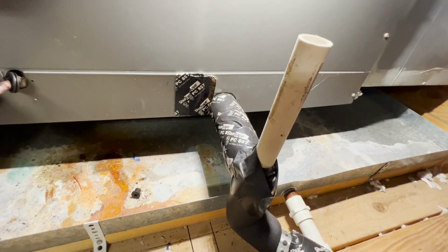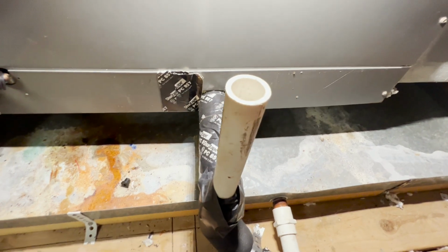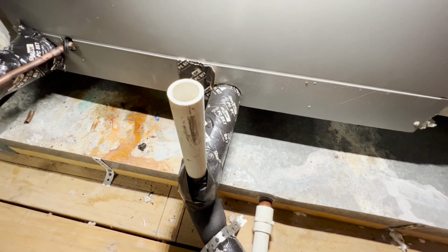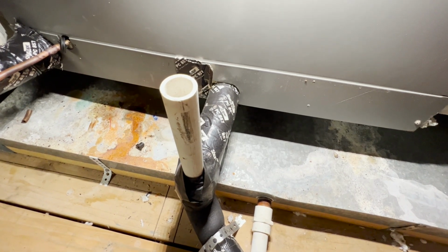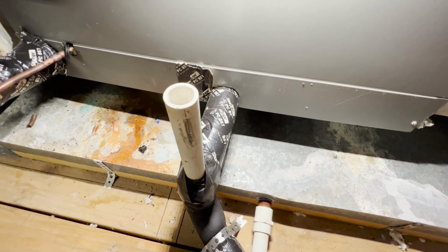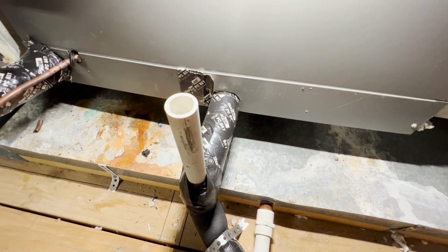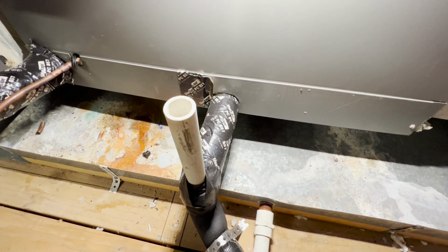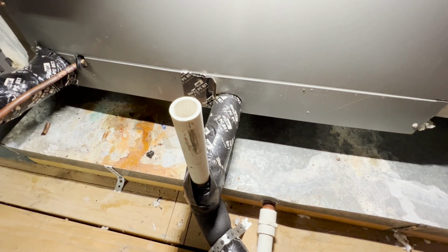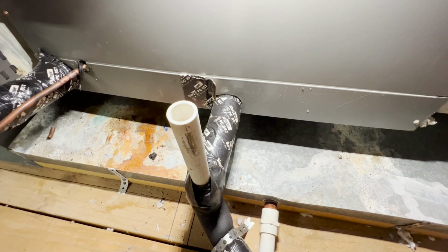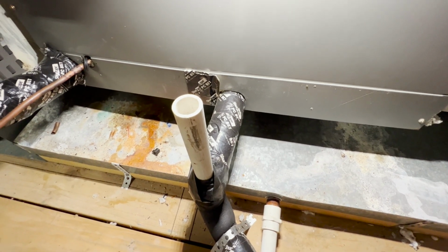One way you can get rid of this clog is just by pouring vinegar down there, and that vinegar over time will dissolve the algae. Another way is blowing compressed air through it. Even bleach or watered down bleach can get rid of the algae. Now, bleach is a harsher chemical. I would recommend using vinegar, but this is the easier of the two clogs to get rid of.